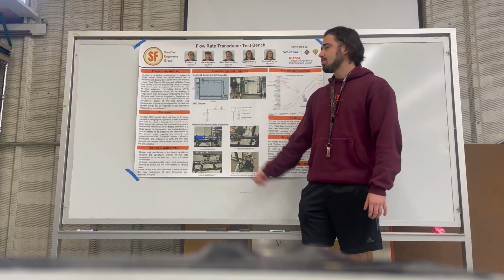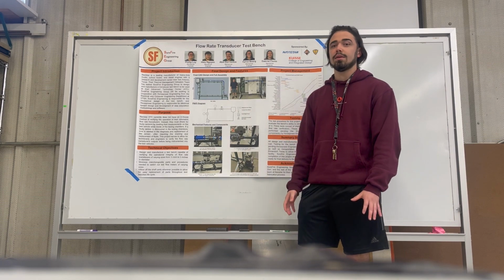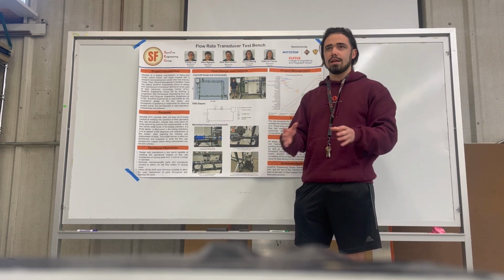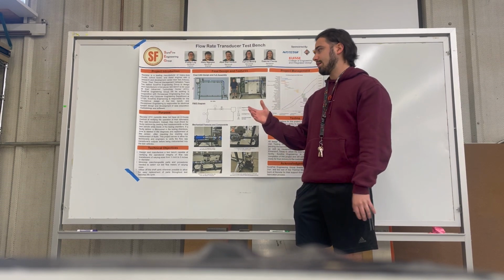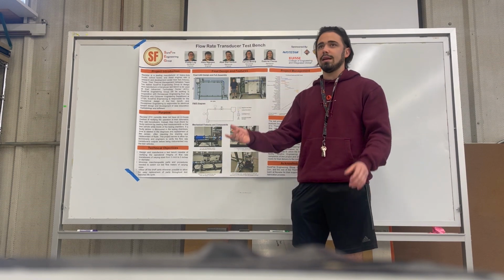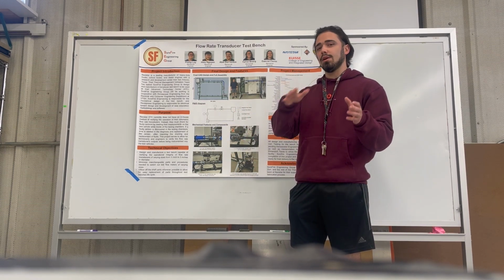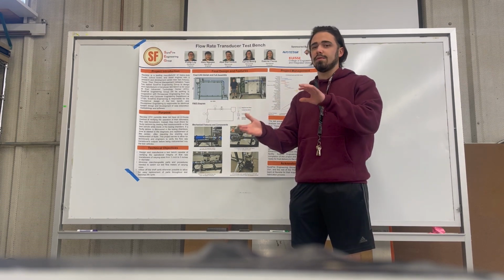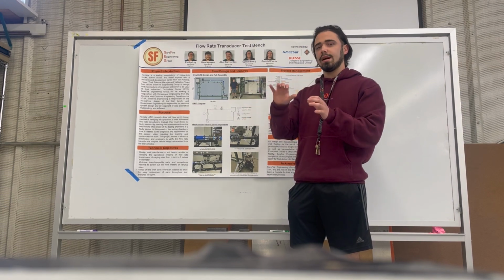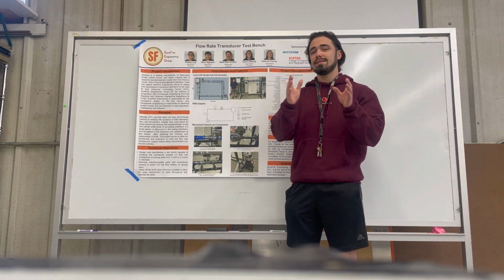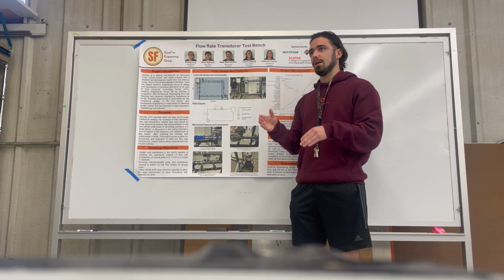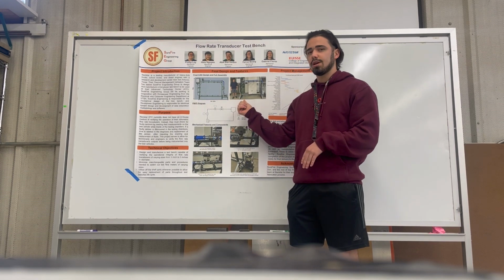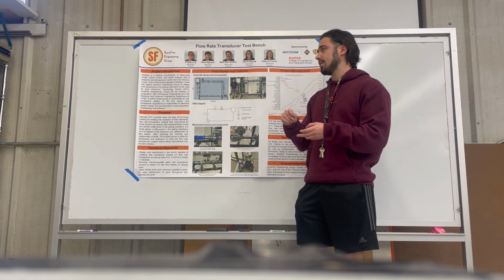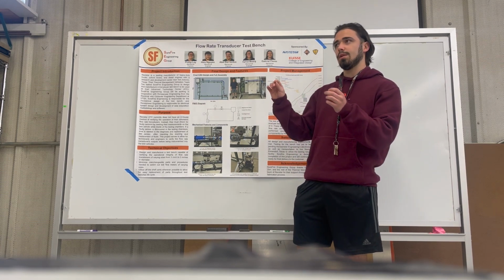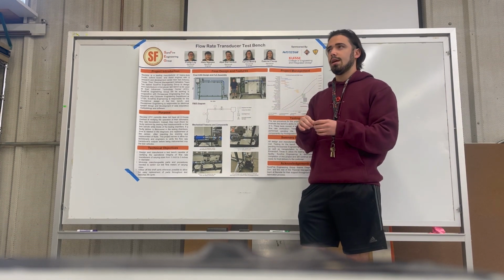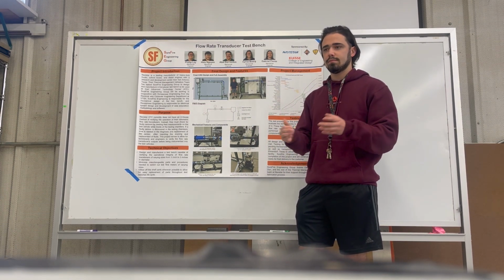So the purpose of the flow transducer test bench is that Navistar right now doesn't have an in-house way of verifying whether the sensors work or not. Instead, while they're testing, they check for these transducers and see if they're faulty or not, and that takes them a long time to verify. That means that they have to end the test, drain out fluid, and that's when they know whether it's a faulty sensor or not. And so this test bench comes in so that we can save time, and it can be a much more reliable system of checking whether these transducers are actually working and whether they're reading their actual output of flow.